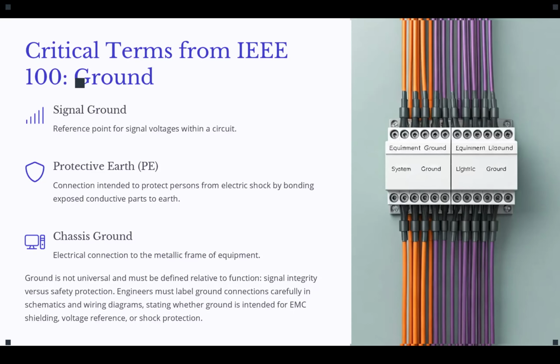If we're talking about protective ground, we're talking about the connection intended to protect persons from electrical shock by bonding exposed conductive parts to the earth. So the simple word ground could mean different things. Chassis ground is normally the electrical connection to the metallic frame of the equipment. When designing electronic, communication, or IT equipment, the ground is the connection that connects the frame of that equipment to the protective ground.